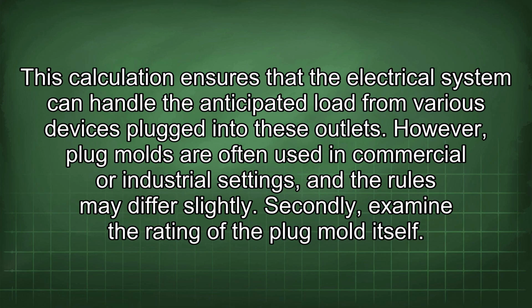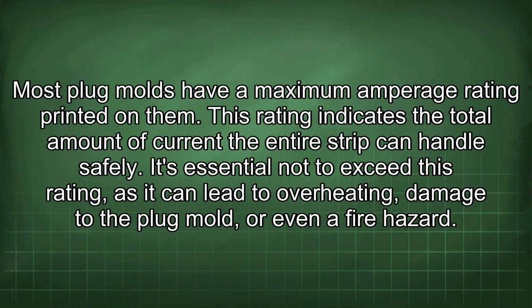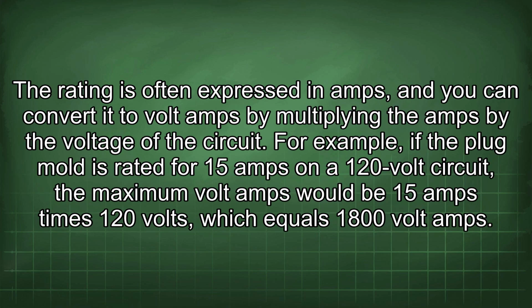Secondly, examine the rating of the plug mold itself. Most plug molds have a maximum amperage rating printed on them. This rating indicates the total amount of current the entire strip can handle safely. It's essential not to exceed this rating, as it can lead to overheating, damage to the plug molds, or even a fire hazard. The rating is often expressed in amps, and you can convert it to voltamps by multiplying the amps by the voltage of the circuit. For example, if the plug mold is rated for 15 amps on a 120 volt circuit, the maximum volt amps would be 15 amps times 120 volts, which equals 1800 volt amps.